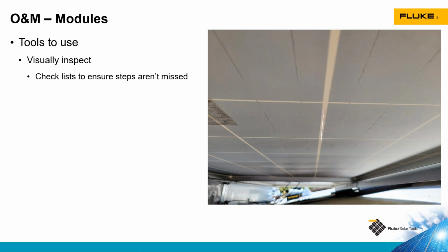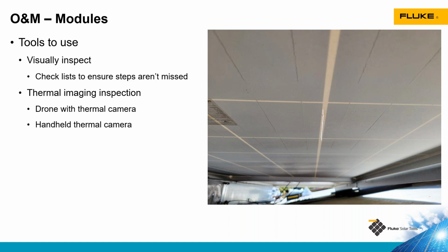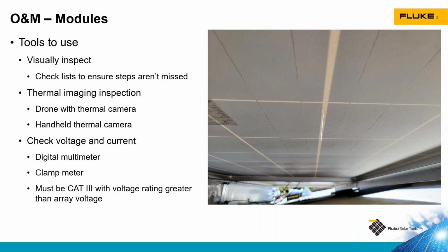During visual inspection of our modules, again, having a trained person to do it is good. Having a checklist to make sure you don't miss anything. Thermal imaging we can do with a drone, we can do with handheld cameras. We have a suite of multimeters and current clamps to measure both voltage and current. Make sure when you're selecting a test tool that it has the proper category and voltage rating for the environment and the voltage that you'll be testing at. So if you're doing testing on the DC side of the system, it's going to be a category 3 environment.